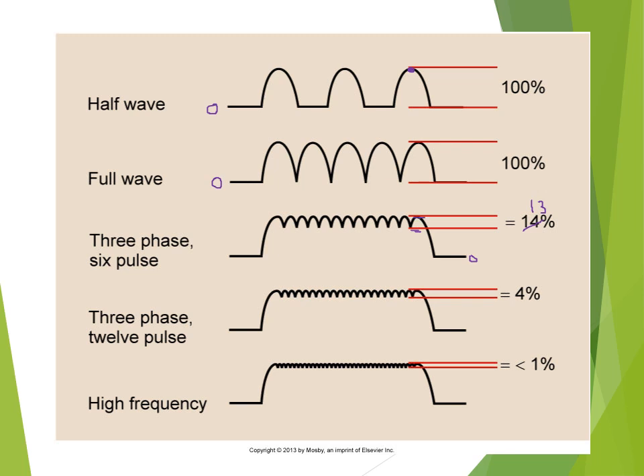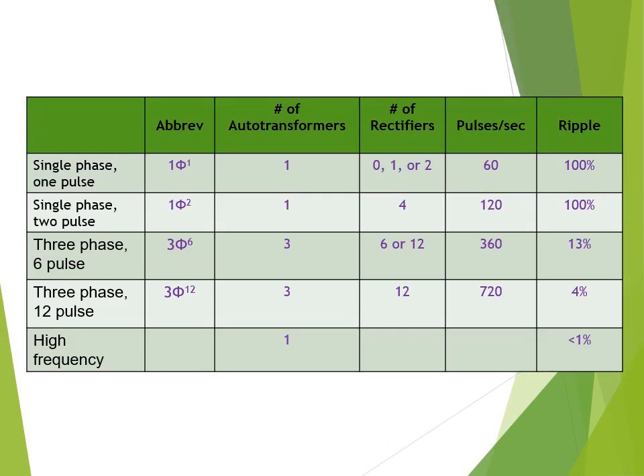It's a 13% ripple. 3-phase 12 pulse is something we can do: we can change the windings of the step-up transformer is all we have to do, and we get 4% ripple. And then high frequency has a ripple of less than 1%. Now, as far as abbreviations, we're looking at this phi symbol being used for the phase. So single phase 1 pulse for the half wave rectification. Single phase 2 pulse is the full wave rectification, which is 1 phase 2. 3-phase 6 pulse is 3 phase 6. And then 3-phase 12 pulse is 3 phase 12.